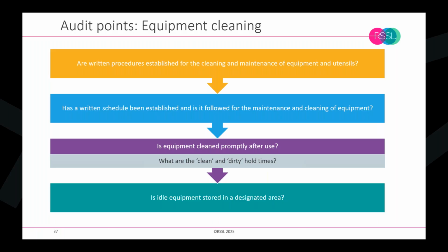We need established procedures of cleaning and maintenance, properly qualified cleaning regimes, and separation of clean and dirty equipment, avoiding wet equipment at all times. After cleaning, we should have good drying procedures, because wet equipment is a fundamental source of bacterial contamination and bacterial endotoxin.